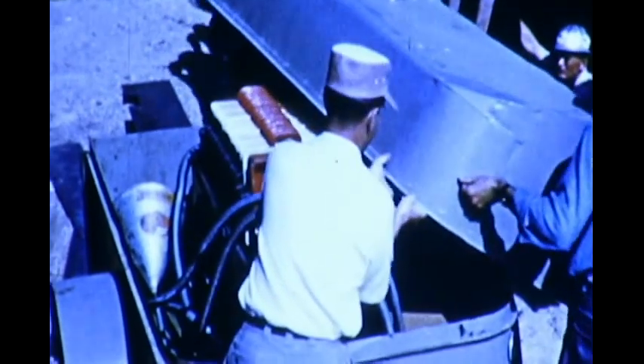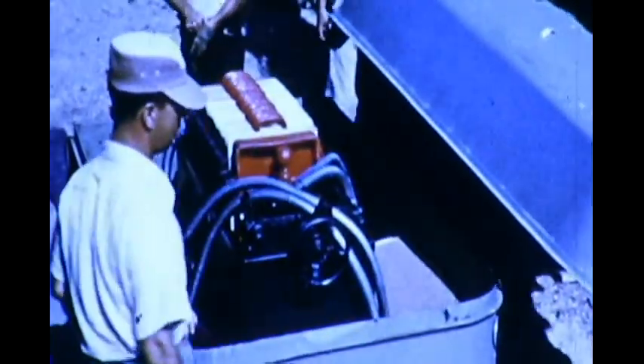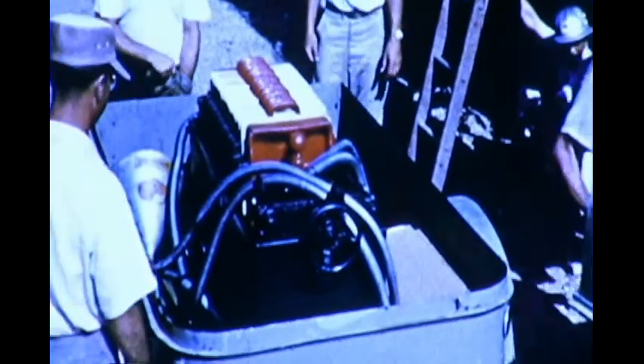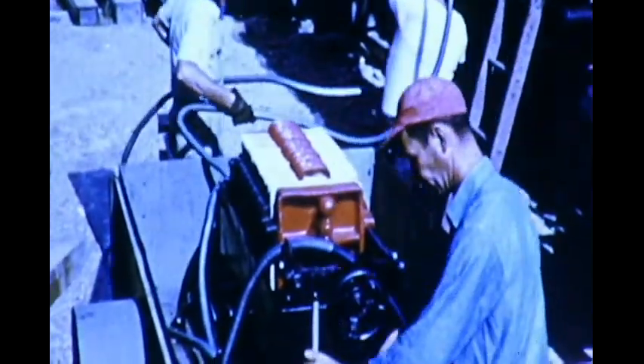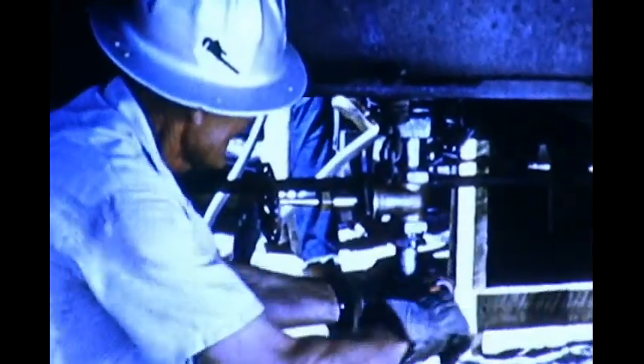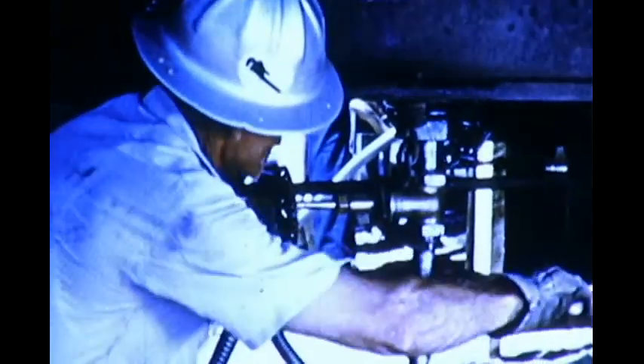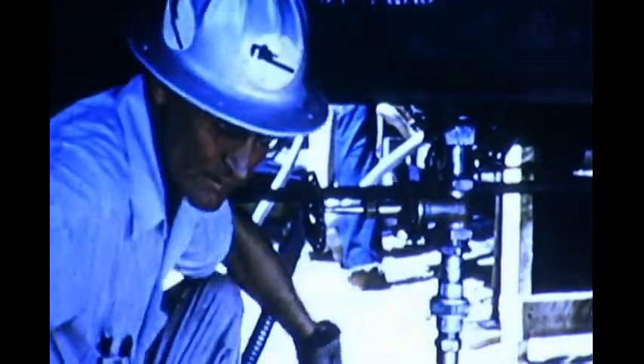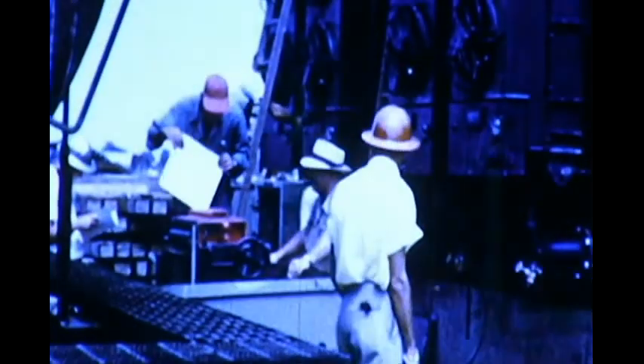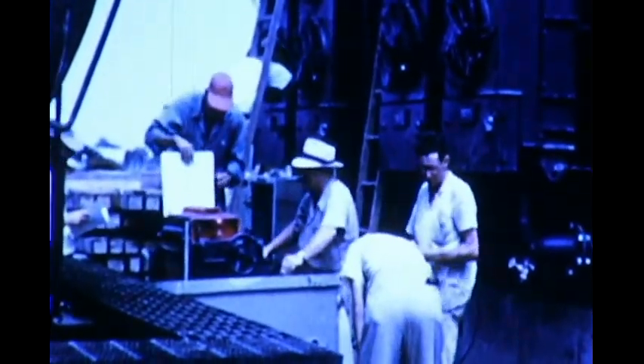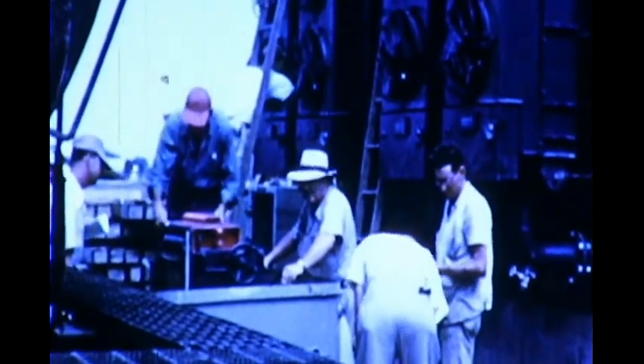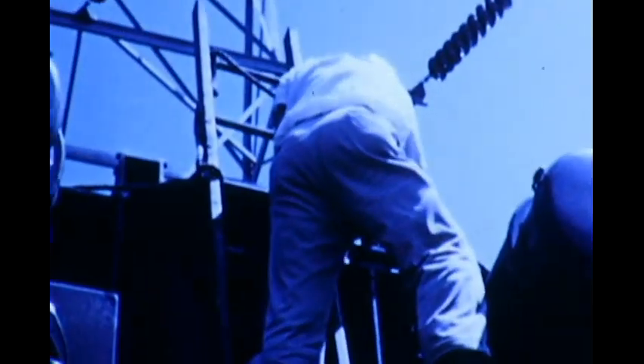Filtration of the oil prevents impurities and moisture from being pumped into the transformer. Had it tested lower than 22 kV, several passes through the press would be made to improve the oil before pumping it into the transformer. Metal piping or oil-proof synthetic rubber hose is preferred for handling the oil. Then, with hot, oven-dried filter paper inserted in the press, we're ready to start pumping. A bypass valve is opened, the pump started, and a small quantity of oil is drained off to flush the system.